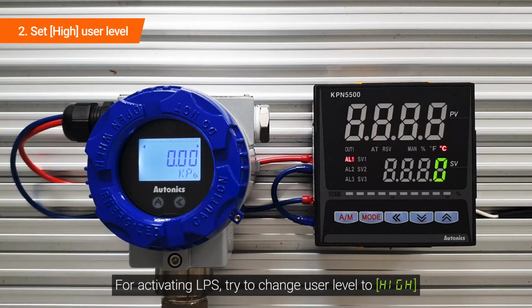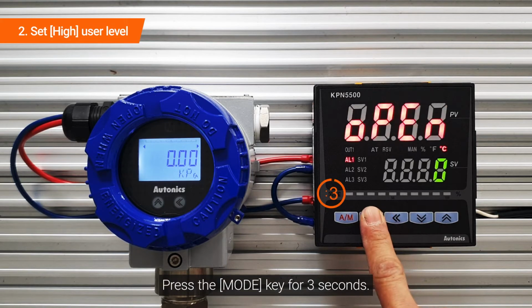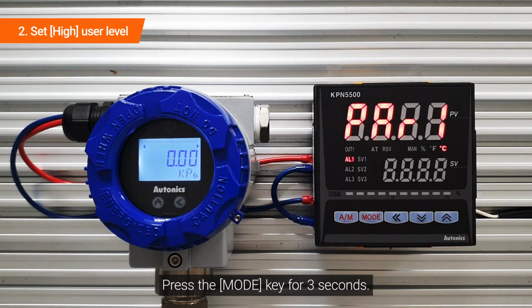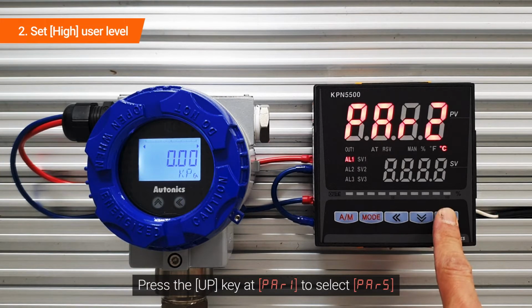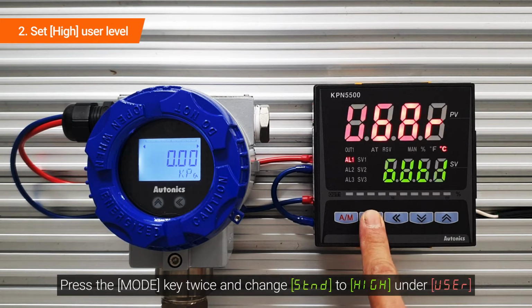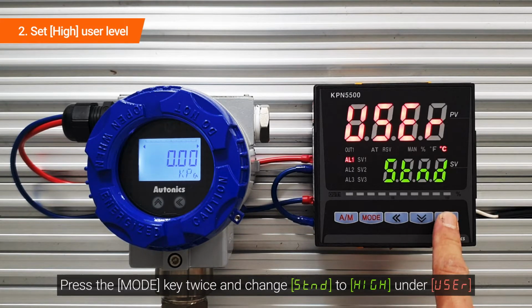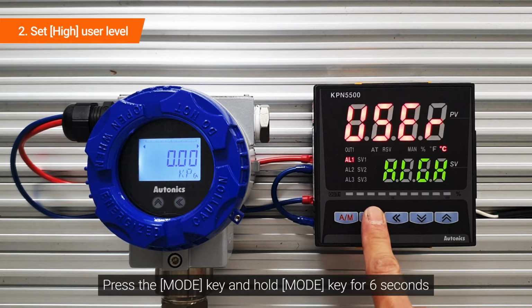For activating LPS, try to change user level to high. Press the mode key for 3 seconds. Press the up key at PAR1 to select PAR5. Press the mode key twice, and change STND to high under user. Press the mode key and hold mode key for 6 seconds.